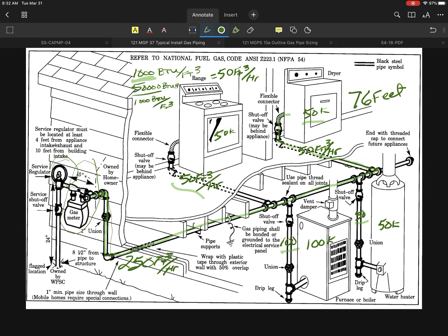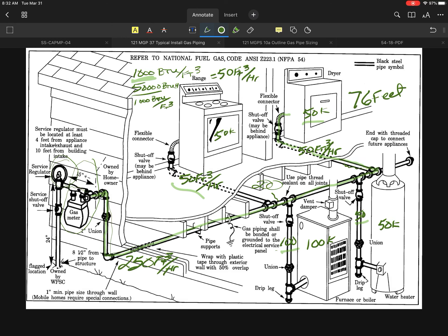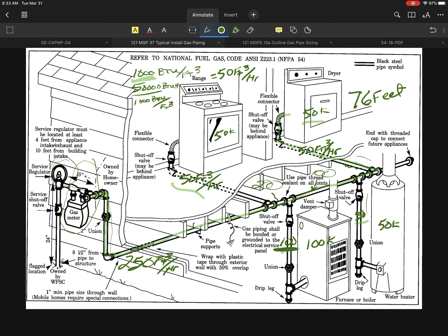This particular section here is going to only have to carry 200, and of course we're going to get rid of 100 after we get through that section, and then we'll be down to the remaining 100. This section here is going to carry the 100, then I'll get rid of 50 down for the water heater, and then the remaining one is going to be another 50.